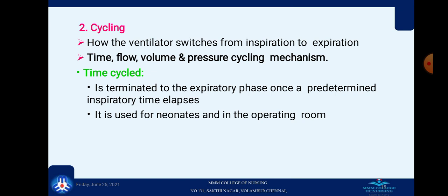Next one is cycling: how the ventilator switches from inspiration to expiration. Time, flow, volume and pressure cycling mechanisms. Time cycle: it terminates to the expiratory phase once a predetermined inspiratory time elapses. It is used for neonates and in the operating room.